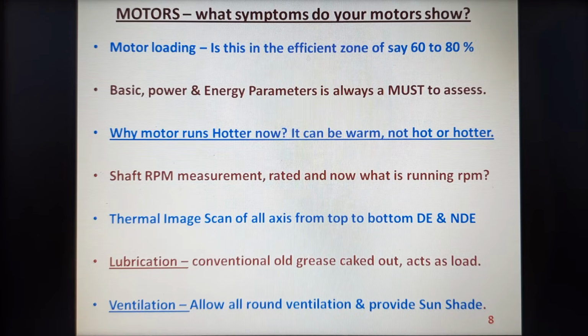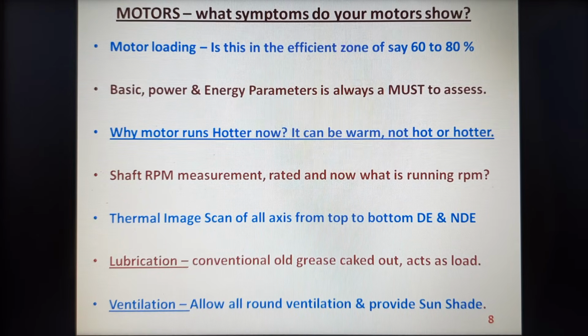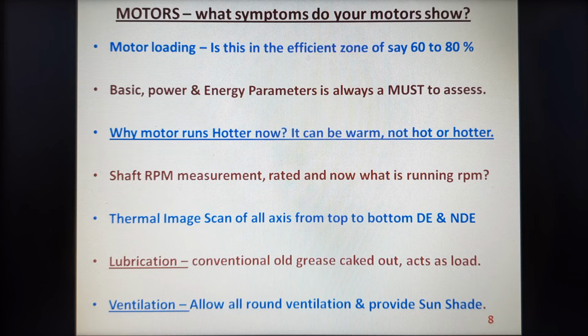Coming to the motors, the motor loading is always efficient if it is loaded around 60 to 80%. You have to monitor the basic power parameters like volt and amps and the kilowatt and kVA, just to know whether the motor is running at the rated capacity, less capacity or more capacity. Why are the motors getting heated up? It can be a warm motor, it cannot be a hot motor or a hotter motor or a cold motor. So an idling motor is always cold, whereas a hotter motor is undersized, it is running overloaded. There the loss is more as such.